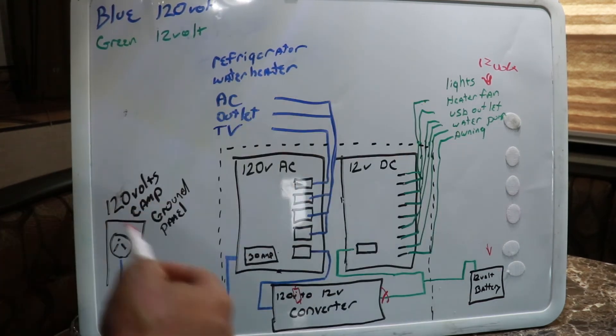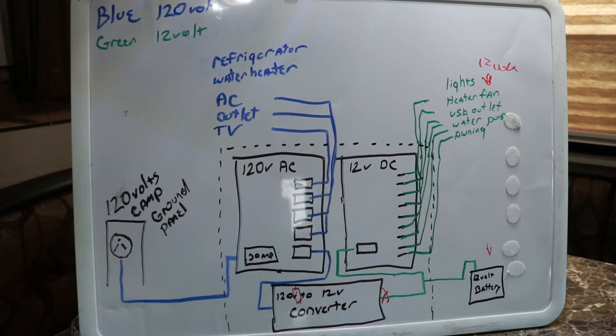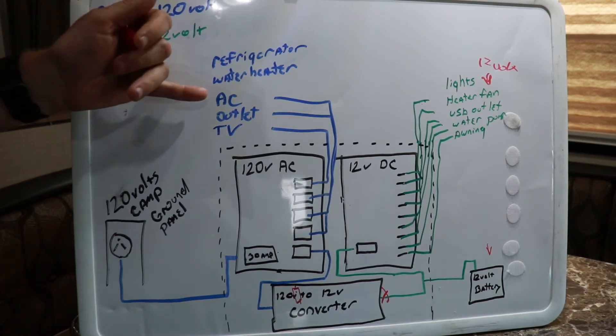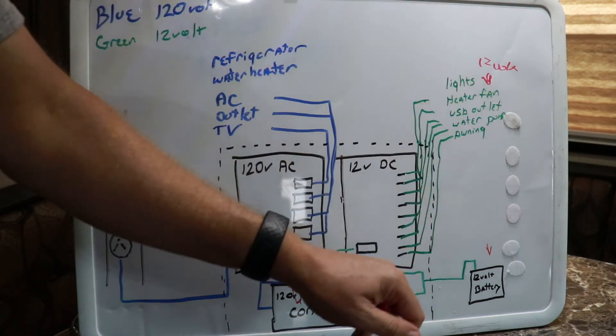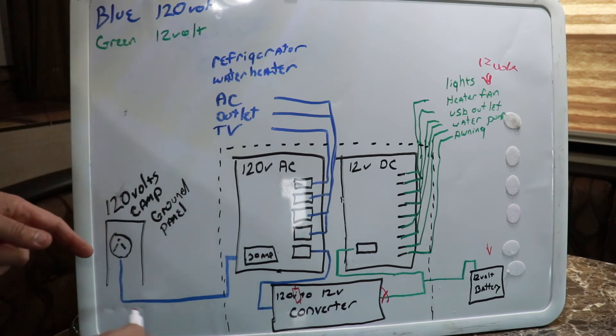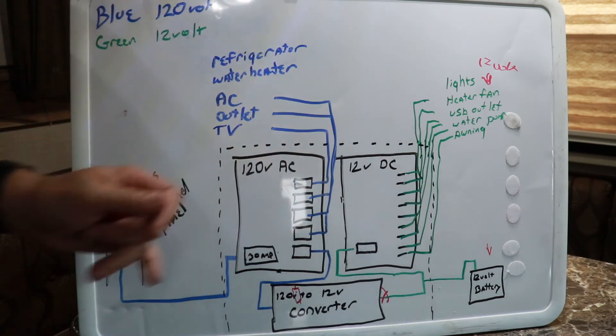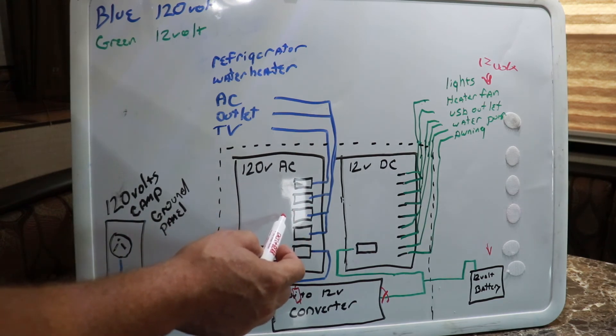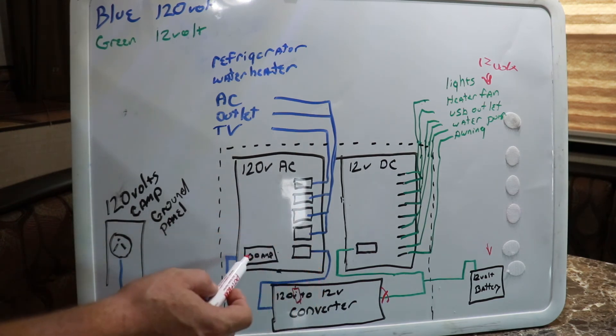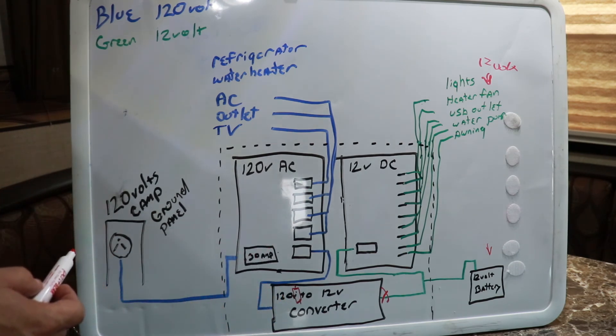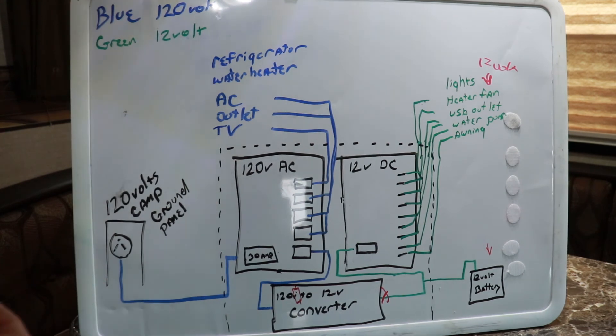As you can see, using this diagram here you could actually go through and troubleshoot anything. If your AC wasn't working, you're not going to be looking at the DC side of it because they don't even affect the DC. So if it's AC, you're gonna check the AC breaker. If that's good, then you'll check your 30 amp breaker coming in. If that's good, then you'll check back here.